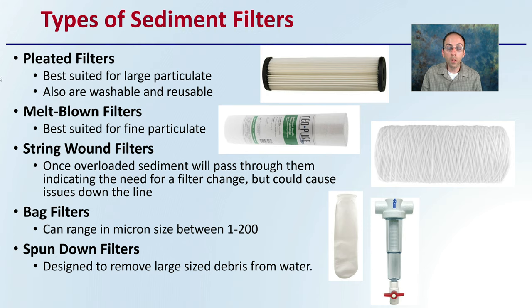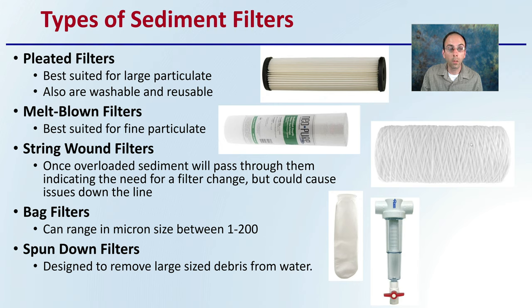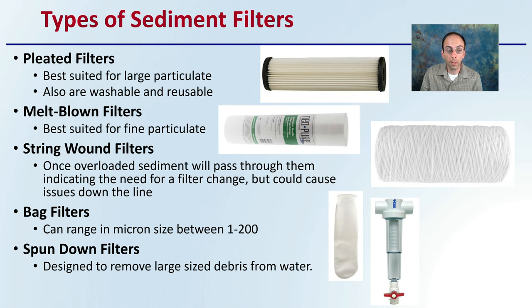What are the different types of sediment filters? Pleated filters are best suited for large particulate and are washable and reusable. Meltblown filters are best suited for fine particulates. String-wound filters, once overloaded with sediment, will pass particulate through, indicating the need for a filter change — but this could cause issues downstream, as it will suddenly let particulates by when full. Bag filters range in micron size between 1 and 200 microns. Spun-down filters are designed to remove large-sized debris from the water. Depending on what you're trying to remove will determine which type is the best option.